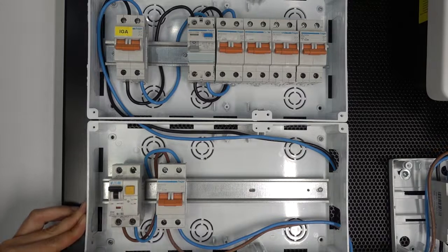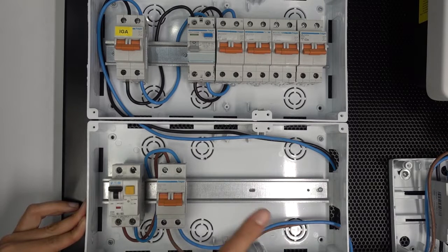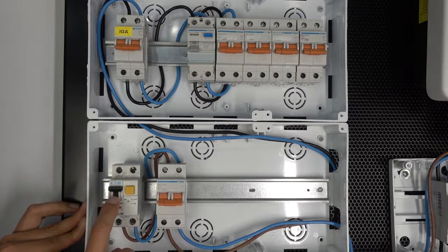So at the end of the video we are going to do some tests to try to jump this differential switch causing a shunt in the grid inverter to see if indeed this line that goes to the grid inverter is protected. So as I say, we are going to make some operation tests, once we have connected all the connections of the grid inverter, to cause a shunt and see if this differential protection, that is so important because it protects people, jumps.